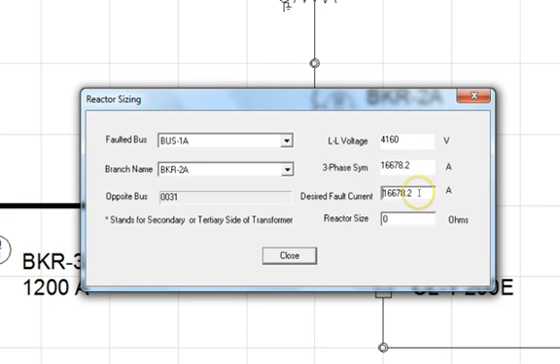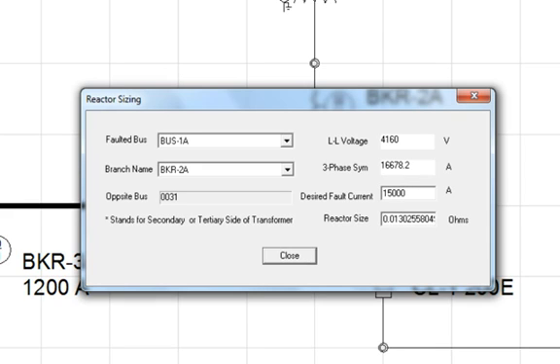Notice that the calculated fault level at this bus is in excess of 16,000 amps. In order to reduce this current to 15,000 amps, place your cursor in the desired fault current field and type 15,000. Then, just press the tab button on your keyboard and the reactor impedance in ohms is displayed in the reactor size field. That's all there is to it.